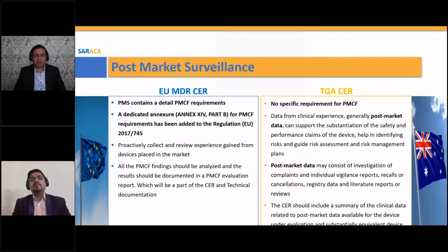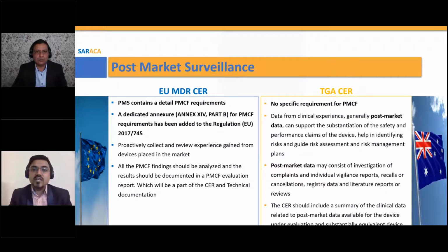In comparison to the earlier directive, there was a wider scope in which you could avoid the PMCF, the post-market clinical follow-up. But in MDR the scope has been reduced, and it is very difficult to justify why a PMCF is not required for your subject device.